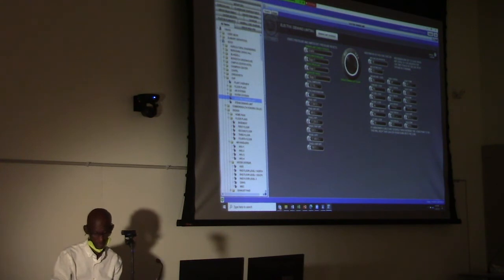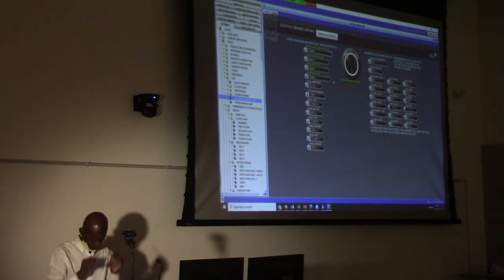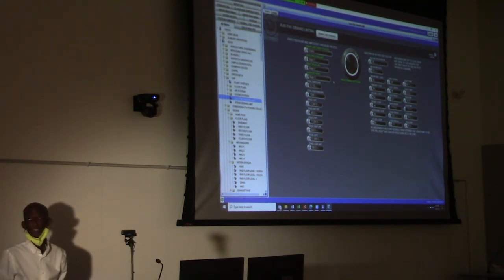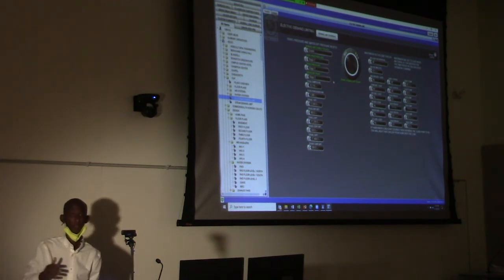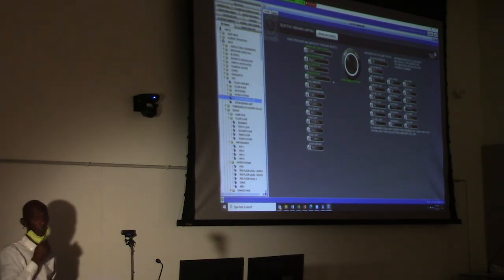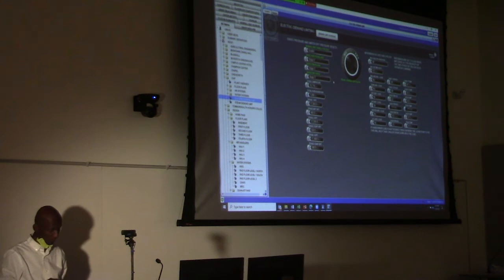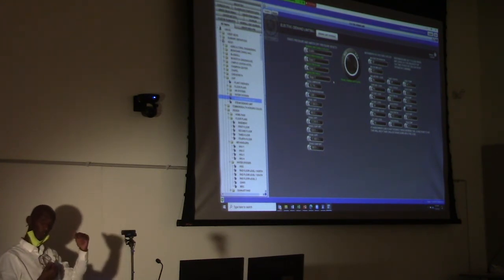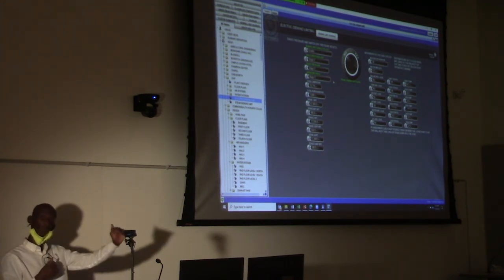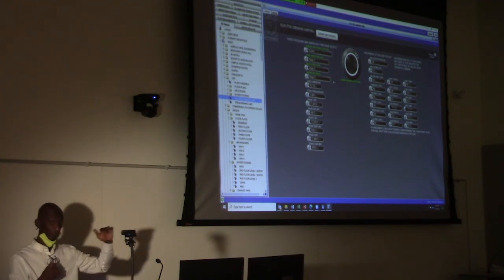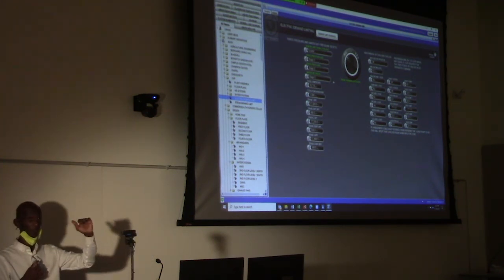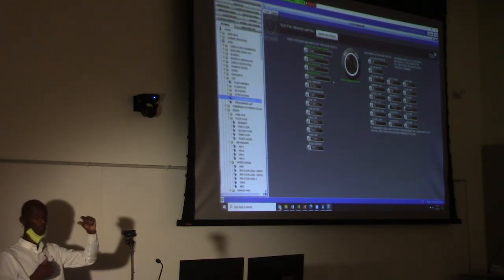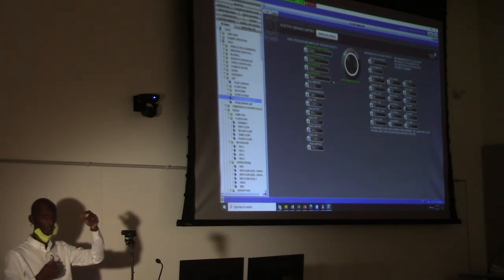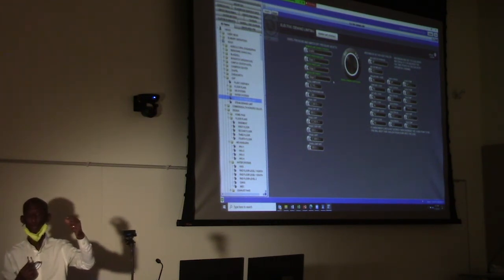And another thing too is we slow down the pumps that feed larger buildings that have to run, mostly the labs. So when we slow down, when we reduce the differential pressure, we have a lower flow. You still have flow in the coils, but because you have a lower flow, you increase the temperature in some spaces by 1 to 2.